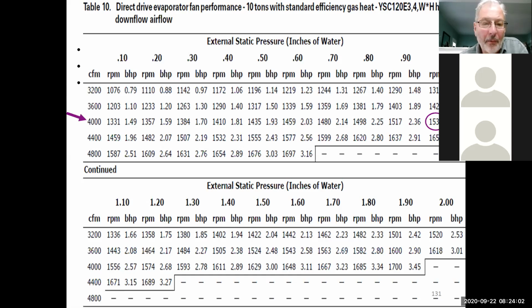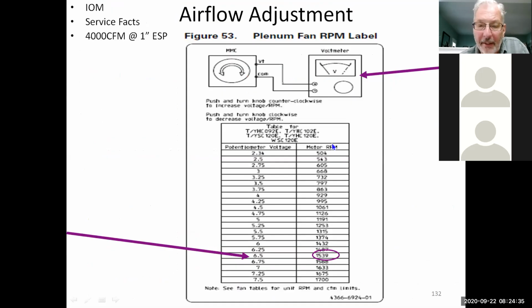Now in this example, we're running an inch of static. Okay, so at an inch of static, 4,000 CFM for a 10-ton unit. Again, that's 400 CFM per ton. I want to get to 1,537 RPM. That's my target RPM, okay? And if you look at it, it gives you the brake horsepower that goes with it. I can't see it there, but I think it's 2.36 brake horsepower. But my target is 1537. So in order to get to that 1537, I need to go to 6.5 volts DC, okay?